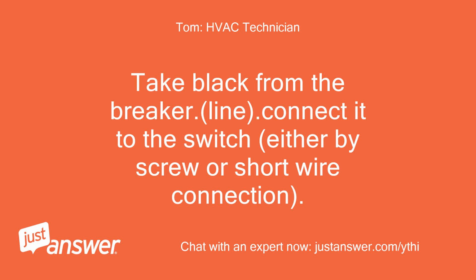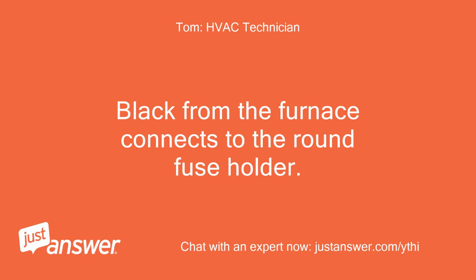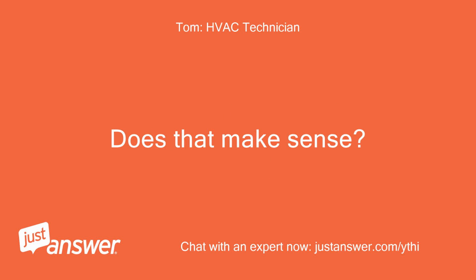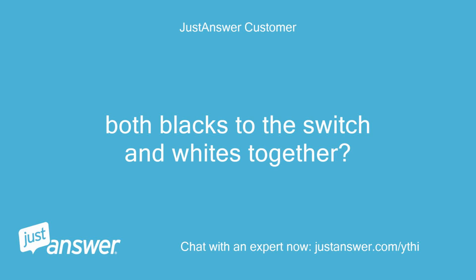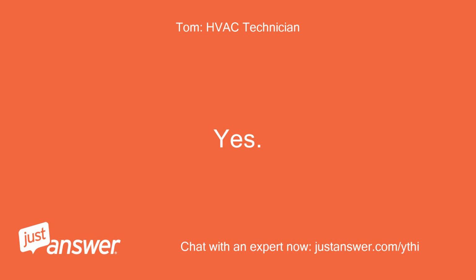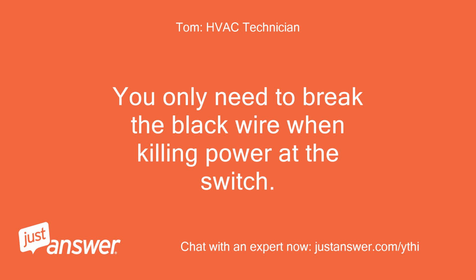Take black from the breaker line. Connect it to the switch, either by screw or short wire connection. Black from the furnace connects to the round fuse holder. Does that make sense? Both blacks to the switch and whites together. Yes. That will work fine. You only need to break the black wire when killing power at the switch.